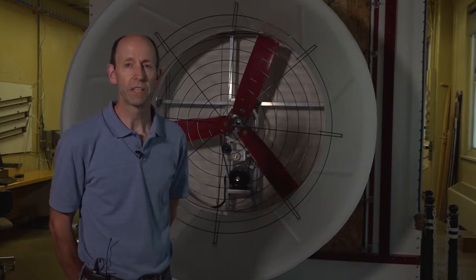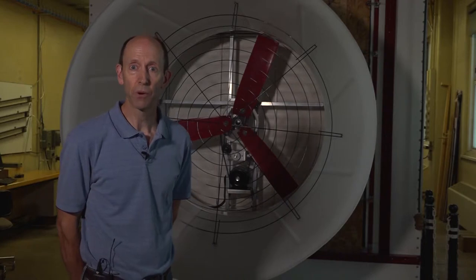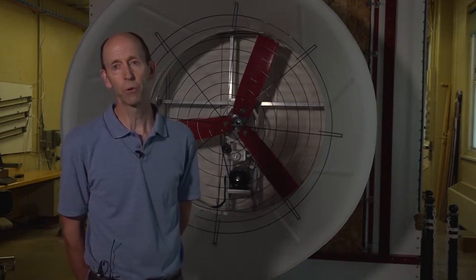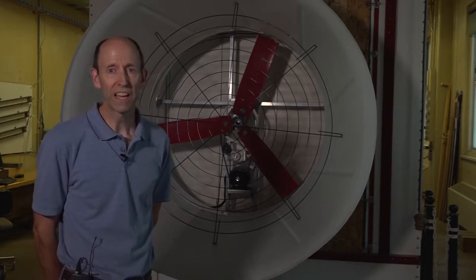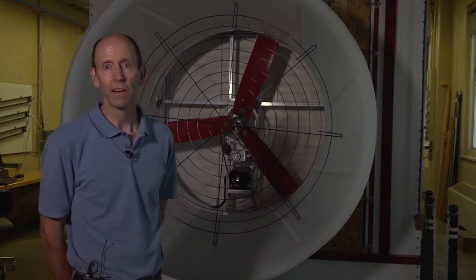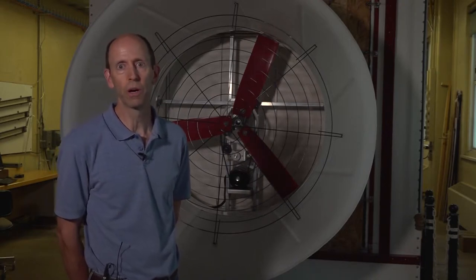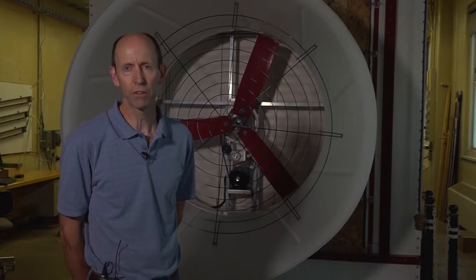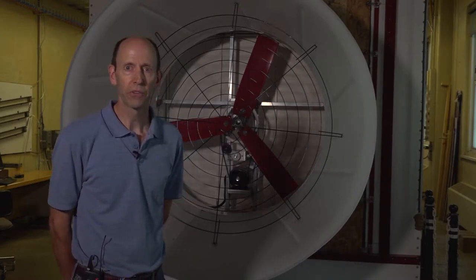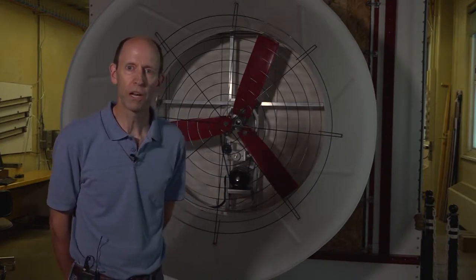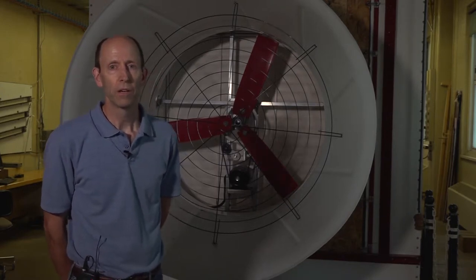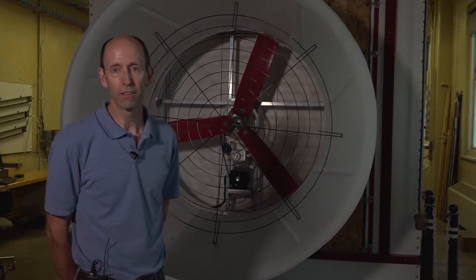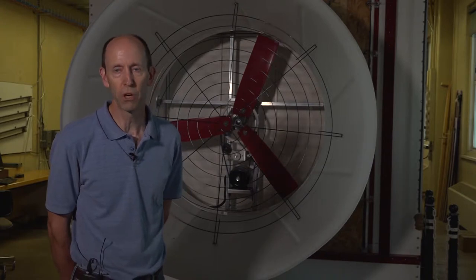The other thing you would want to consider for these two measurements is how does the fan operate at different pressures. Just like with a water pump or any kind of fluid pump, basically a fan is just an air pump. So just like with a water pump, you have different characteristics. You have say a deep well pump where you're pumping against very high pressures to lift the water, but probably a small volume. You might compare that to say a transfer pump where you're pumping a large volume from one tank to another, but you don't have to lift it very high, so it doesn't take the kind of pressure to move that.